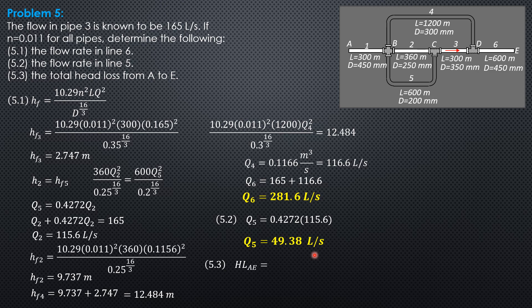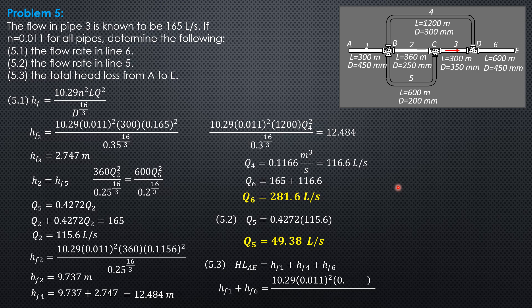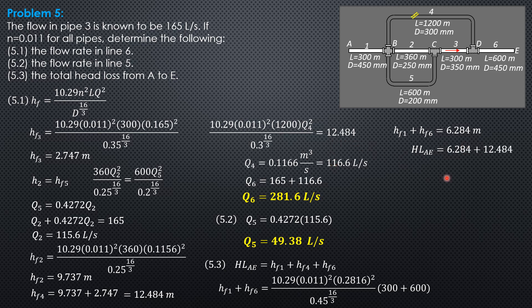Then the total head loss from A to E is HF1 plus HF4 plus HF6. The combined discharge of lines 1 and 6 is common — 10.29, N², Q², and diameter are shared, so only the length differs. HF1 plus HF6 equals 10.29 times 0.011² times 0.2816² over 0.45 to the 16/3, times a length of 300 plus 600. So HF1 plus HF6 equals 6.284 meters. The total head loss is 6.284 plus 12.484, giving a total head loss of 18.77 meters.